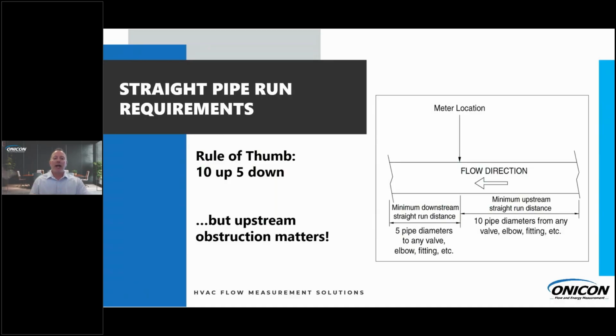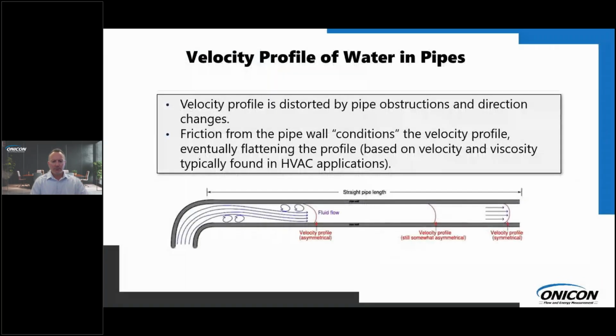And there's certain items that we try to avoid: modulating valves, inflowing tees, outflowing tees, and so forth. And that can greatly increase that straight run obstruction. So if that's what you're dealt with and you have an ample amount of straight run, we typically go with the 80% upstream and 20% downstream in those specific scenarios.